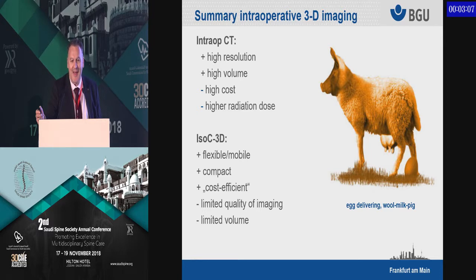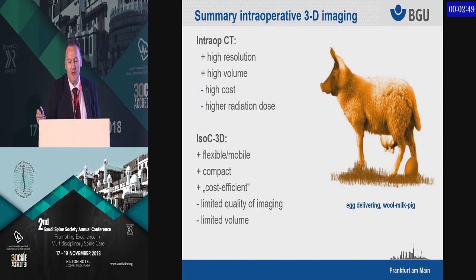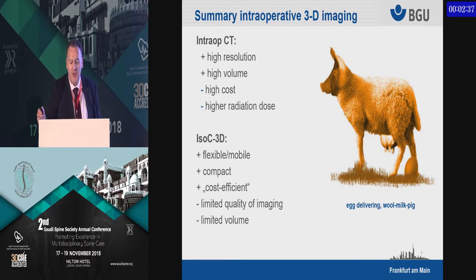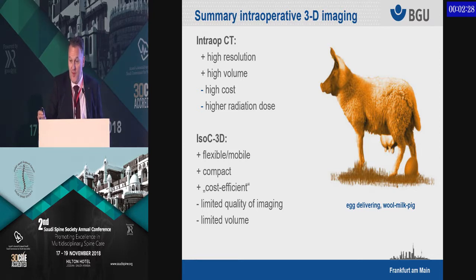What we call in Germany an 'eierlegende Wollmilchsau' — the egg-laying wool-milk pig — does not exist. In other words, you have to make compromises. If you want an intraoperative CT scanner, you get high resolution and high volume, but you have high costs and high radiation doses. On the other hand, if you use the IsoC-3D scanner, you are flexible, mobile, compact, and cost-efficient, but with limited imaging quality and limited volume.